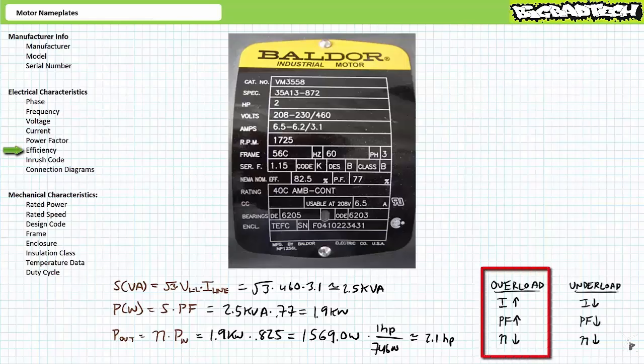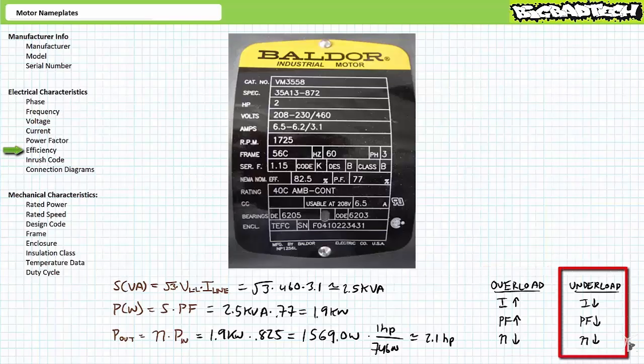Overload conditions might be associated with more current, higher power factor, and poorer efficiency. Underload conditions might be associated with less current, lower power factor, and poorer efficiency. Oftentimes, the rated condition is a region of peak efficiency, or nearly so. We'll examine electrical properties of three-phase AC squirrel cage induction motors in greater detail in later lectures.